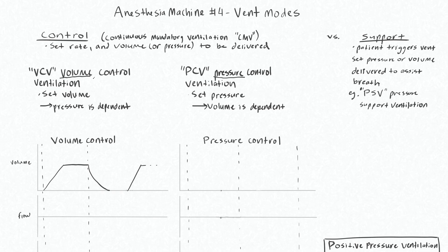Volume control is sometimes called VC-CMV because it's a continuous mandatory ventilation mode that is volume control. Pressure control is sometimes called PC-CMV. Just remember that these control modes differ from support, where the patient actually triggers the vent to assist them with delivering a set volume or pressure. Pressure support ventilation would be a patient-triggered breath that is then supported up to a certain amount of pressure. Let's look at some volume, flow, and pressure curves now.